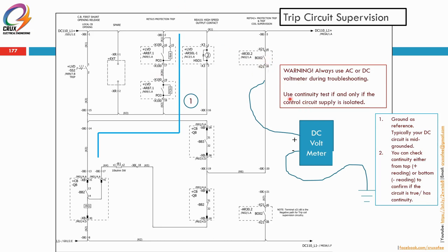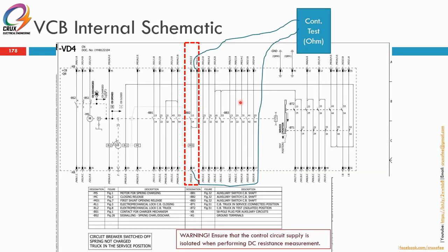So remember, if you want to check any control circuit, you must ensure that you use an AC or DC voltmeter first. You can only use continuity test if and only if the control circuit supply is isolated. Okay, so this is in the case of a mid-grounded DC. Okay, so this is a continuity test. If you want to do it, you can check whether the coil is healthy or not. You can measure the resistance of the coil through this contact. So breaker you rack out, identify the terminals 31, 41, 42, then you measure the resistance. The resistance of the coil you can get from your OEM manufacturer. Again, reminder, if you want to do continuity test, control circuit supply must be isolated before any DC resistance or continuity is performed.